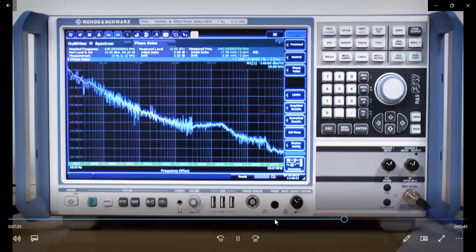Therefore, the oscillator should have a noise performance better than the signal being measured by about 10 dBs. Other techniques like cross-correlation are present in phase noise measuring systems, and this overcomes the issue. But these systems are normally very specialized and much more expensive.